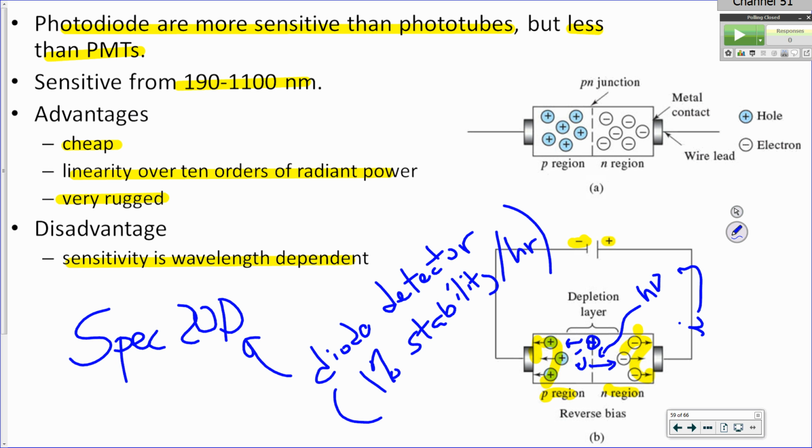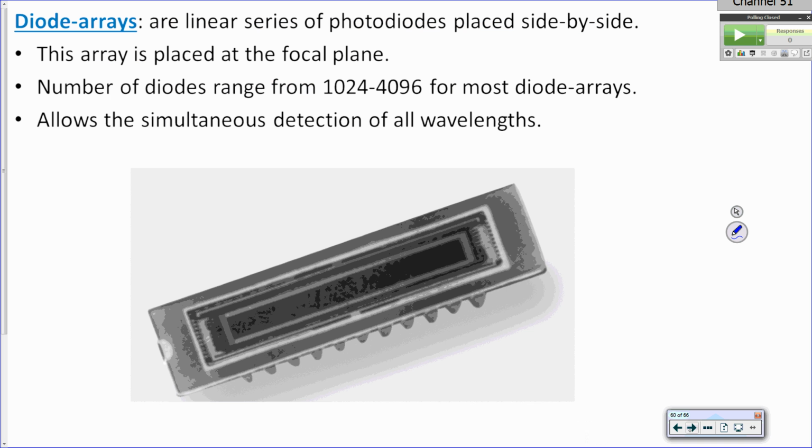The old phototubes, especially, were very temperature sensitive, and you couldn't go 5 minutes, you'd have to recalibrate. I mean, they sucked. You get into doing measurements and doing calibration, and you put in check 100% T that you'd set an hour ago, and it's down at 80%. Like, shoot, start over. It was rough. The photodiodes made life better.